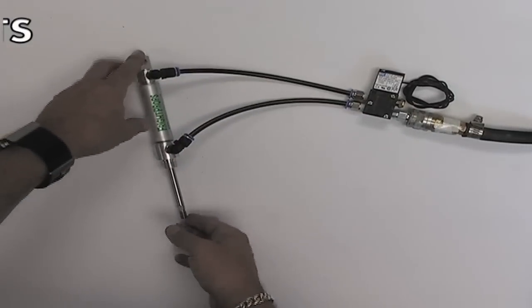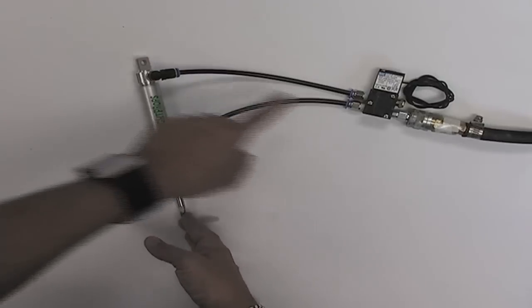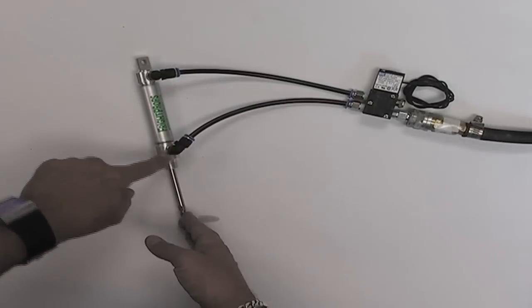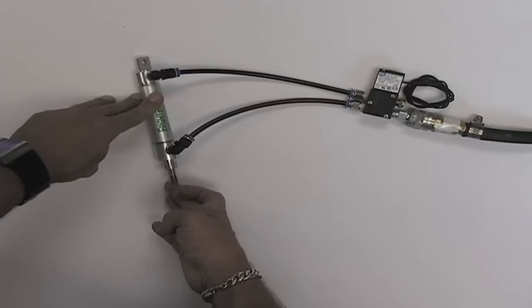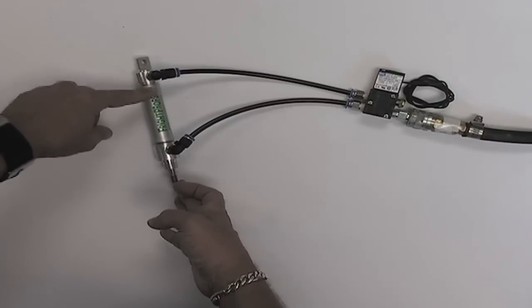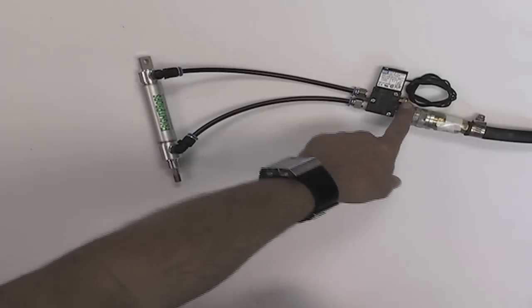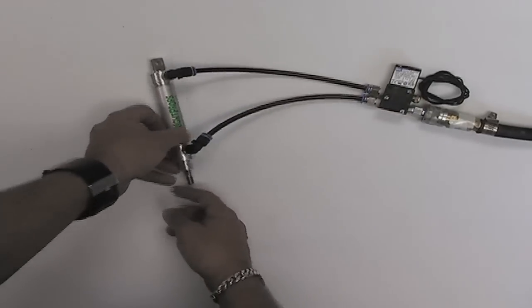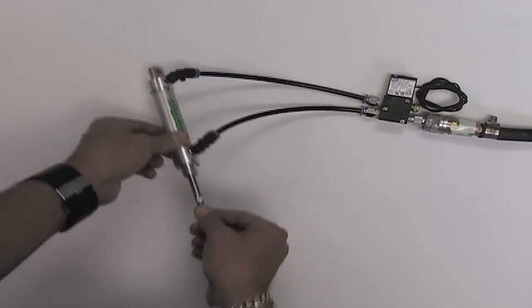Then when we turn it off or de-energize the solenoid, air is going to push through the top again, pushing this shaft back, moving air back out through this air line and out through the same exhaust. By activating the solenoid rapidly, you can make it go in and out.